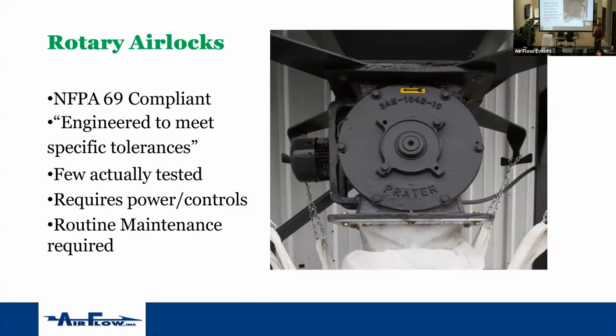There's a lot of rotary airlocks out there on the market right now. Not all of them are tested by NFPA. And the reason they get tested to NFPA, as those vanes turn inside of your rotary airlock, the tolerance between the blade and the sidewall as it rotates, you have to keep a certain tolerance to protect that explosion and pressure flame from coming back into the device at the bottom. It does require power, it requires controls, and requires routine maintenance.